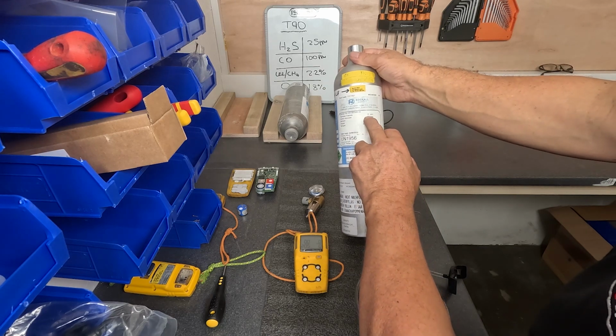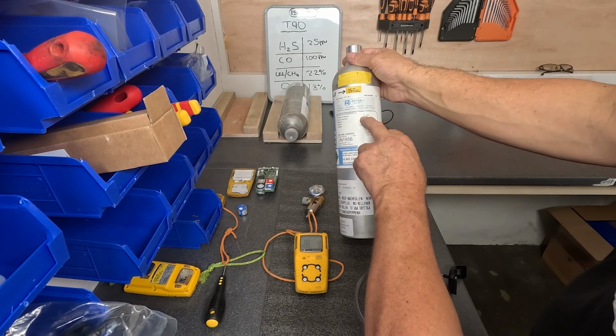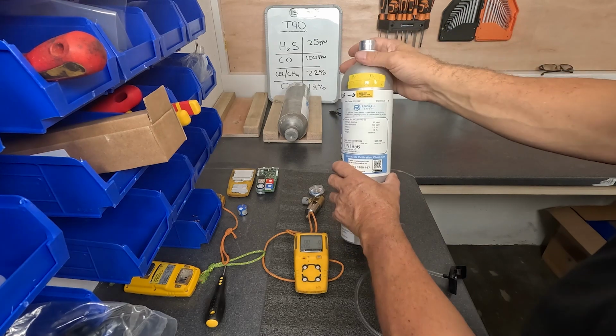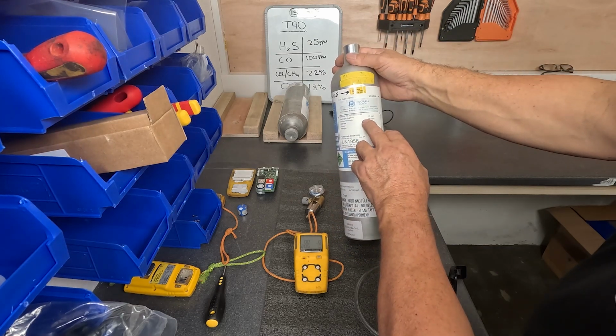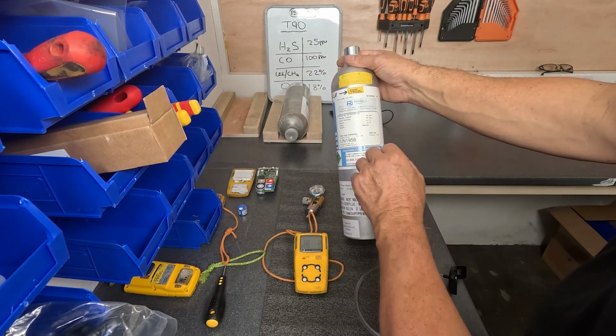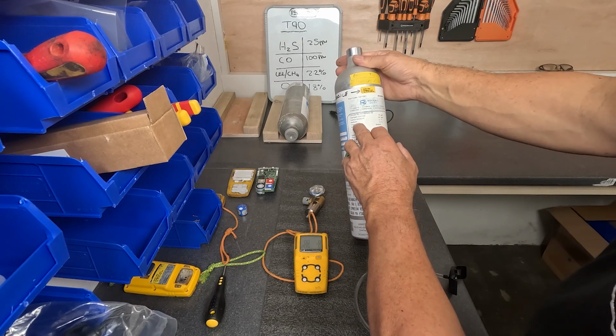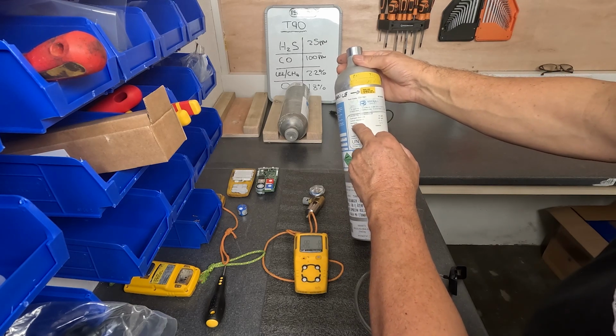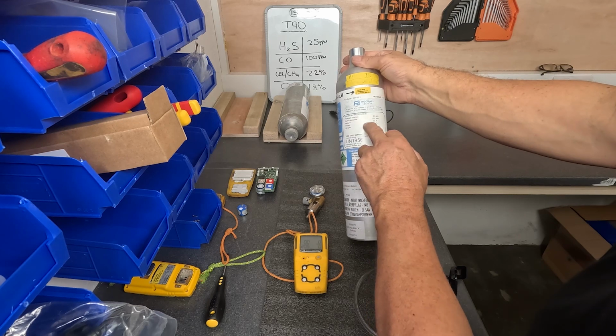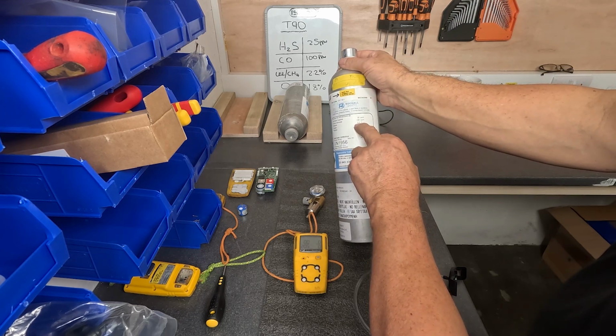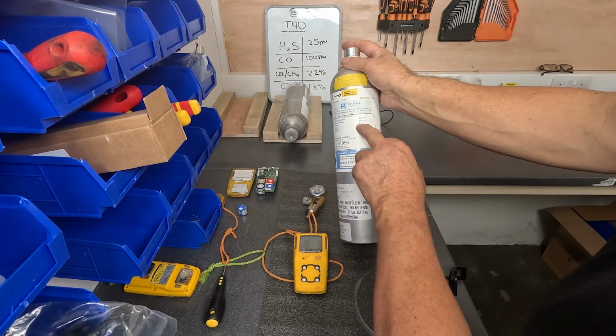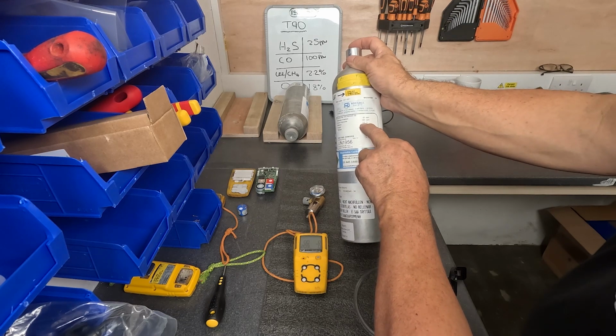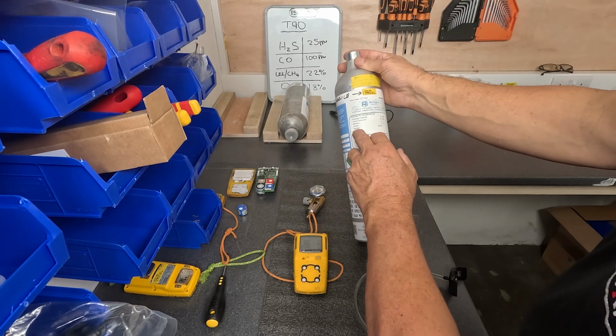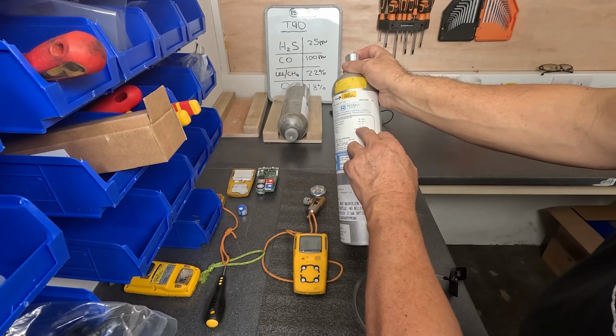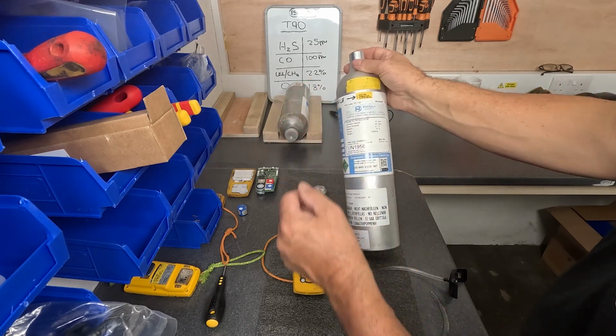So this particular one is set up with hydrogen sulfide at 25 parts per million. I've written it up on the screen at the back so you can see it. The carbon monoxide in here is at 100 parts per million. The LEL sensor, which is calibrated off methane on this detector, so 2.2% volume of the air is 50% of the LEL for methane. And then oxygen is in there at 18%, the balance being nitrogen.